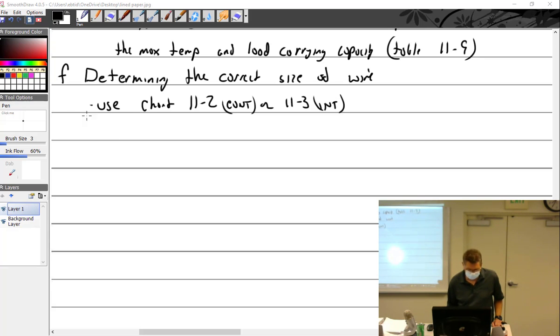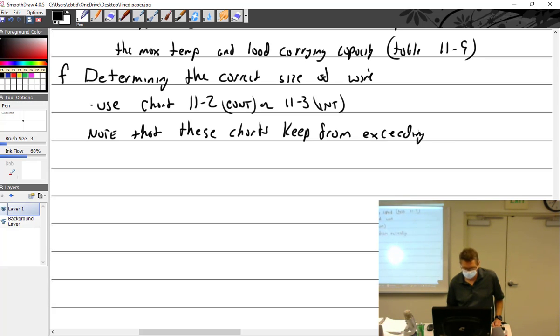Or 3 intermittent. Note that these charts keep you from exceeding the maximum voltage drop. We talked about the maximum voltage drop for each type of voltage system, whether it be 28, 14, or the higher ones. These charts are already set up to make sure you don't do that, so it's not like you have to do this and then that. This works for that.